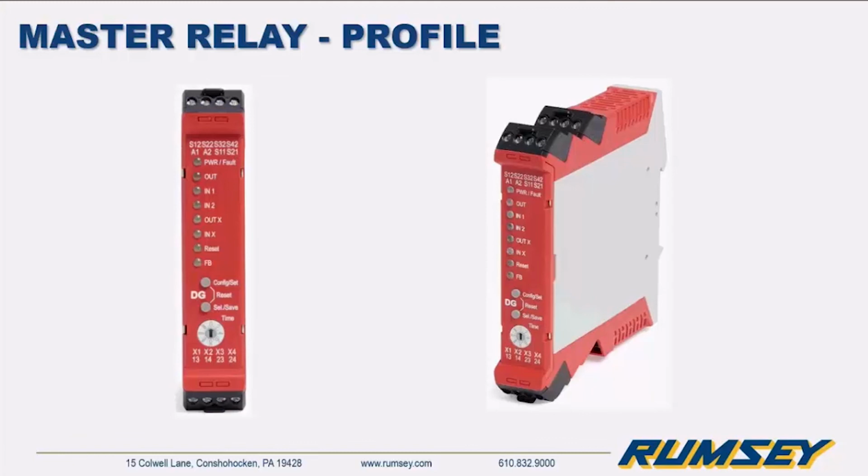What the DG relay does is send a safety pulse through the GuardLink chain, and it determines which one is the last in the series, and then it essentially counts backwards from that through the devices, of which you can have up to 32 connected in series. That safety pulse allows the relay to know which device tripped. At the top there you can see the terminals, and it is also able to do remote resetting.